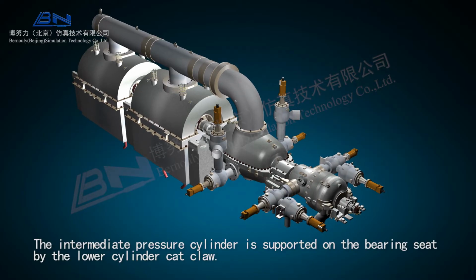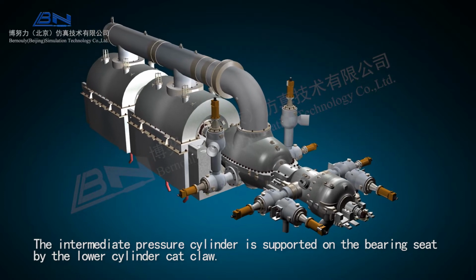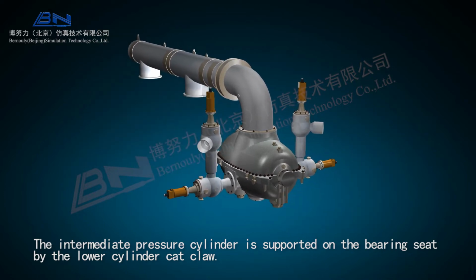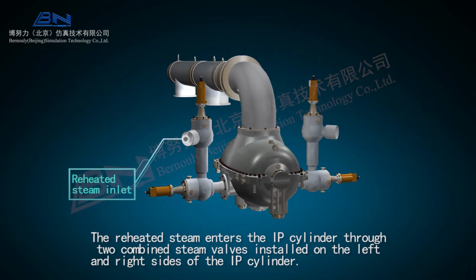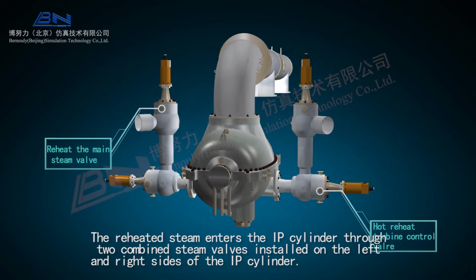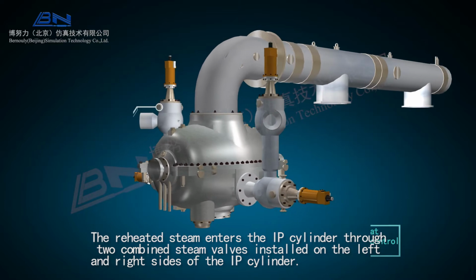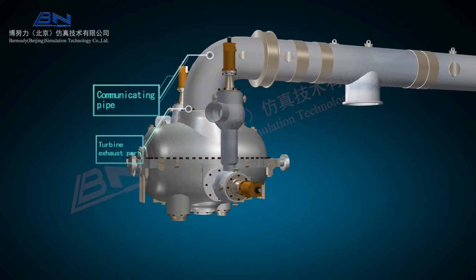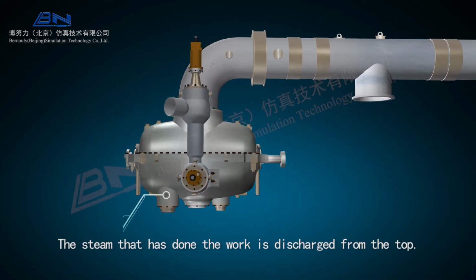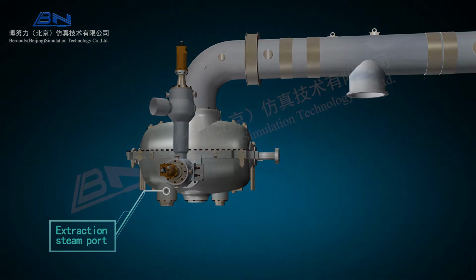The intermediate pressure cylinder is supported on the bearing seat by the lower cylinder cat claw. The reheated steam enters the IP cylinder through two combined steam valves installed on the left and right sides of the IP cylinder. The steam that has done the work is discharged from the top.